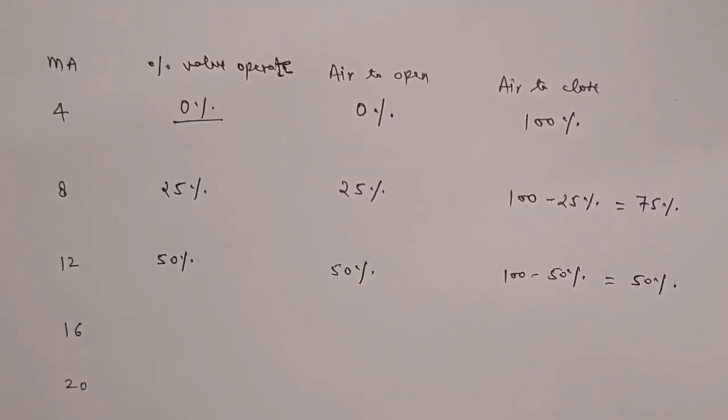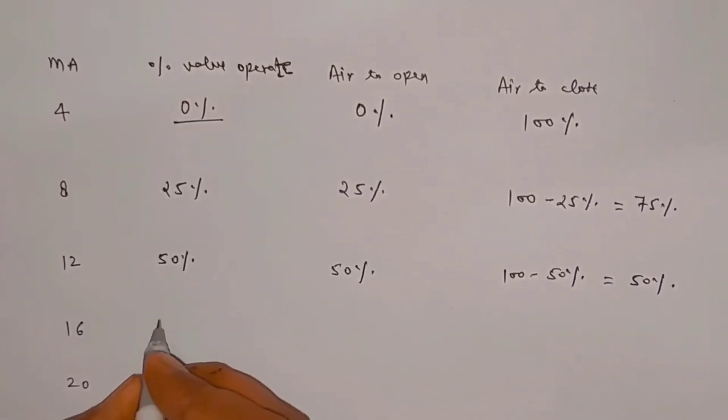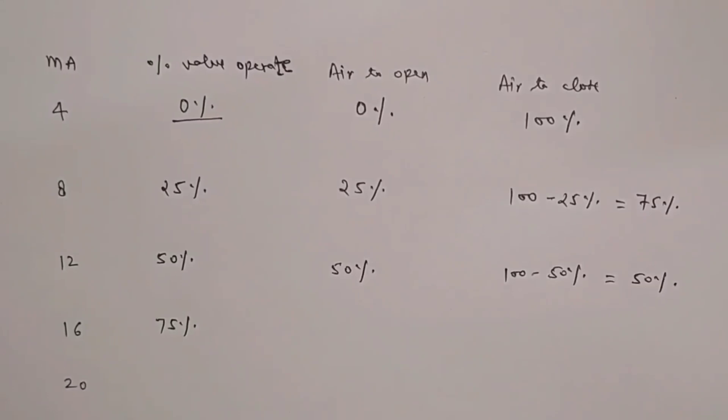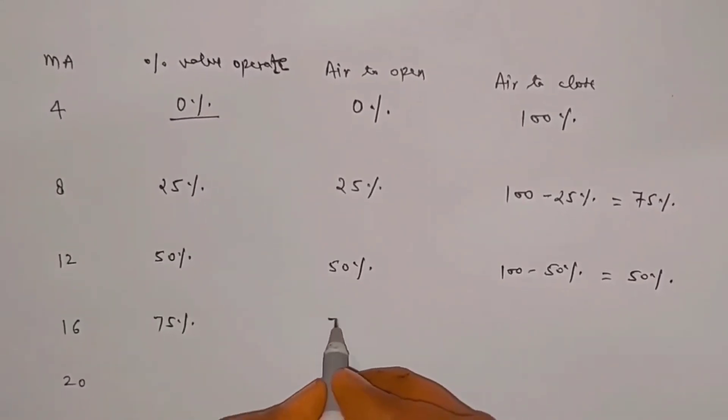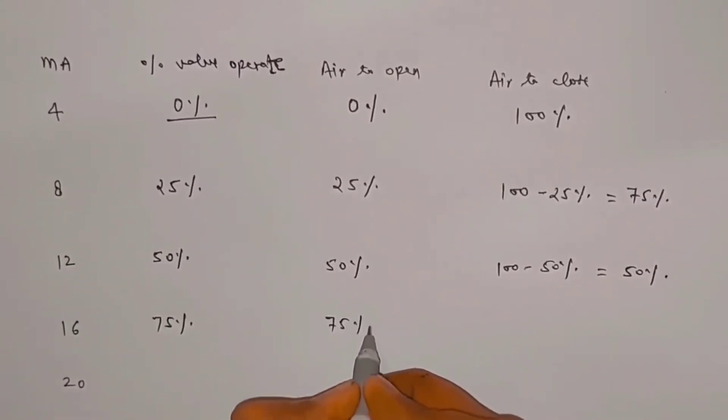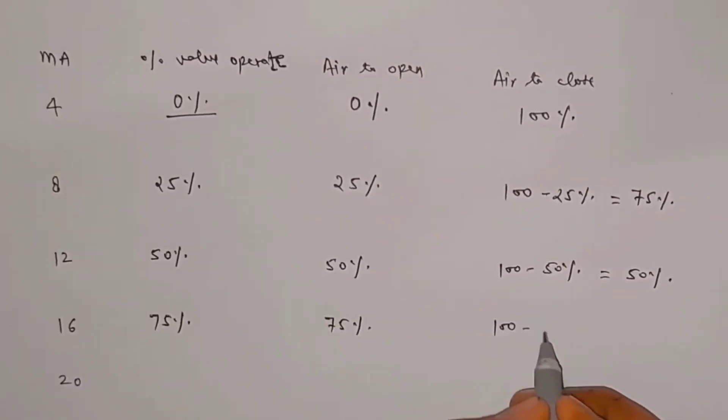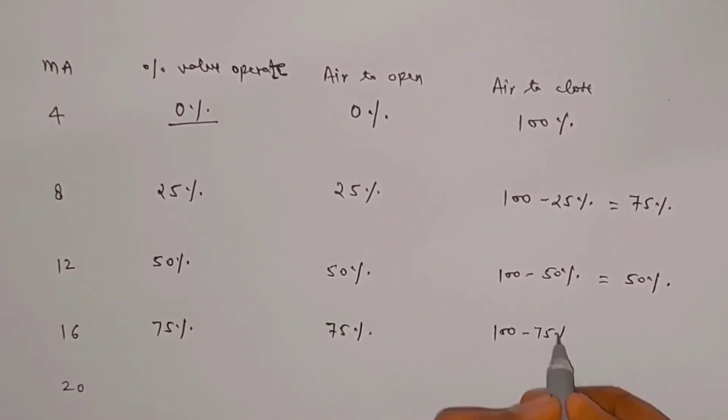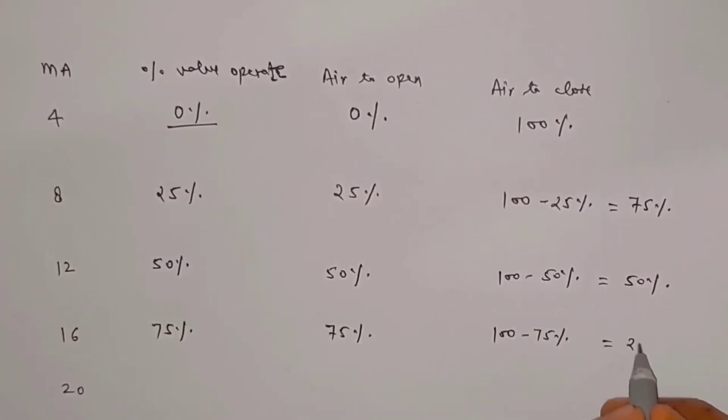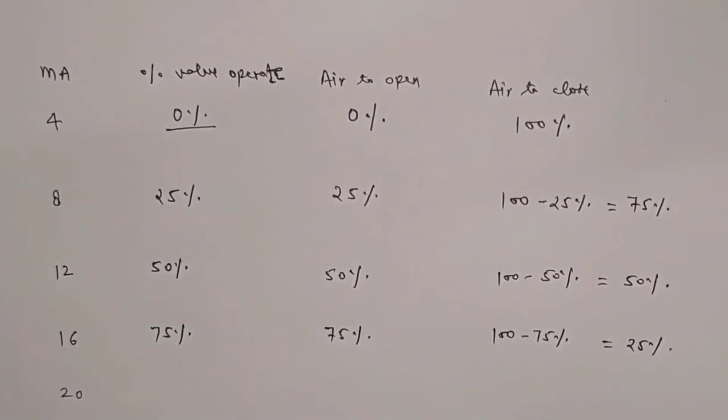Similarly, at 16 milliampere signal, valve operate percentage is 75%. So air to open control valve opening will be 75%. And air to close control valve opening will be 100 minus 75%, so it will come 25%.